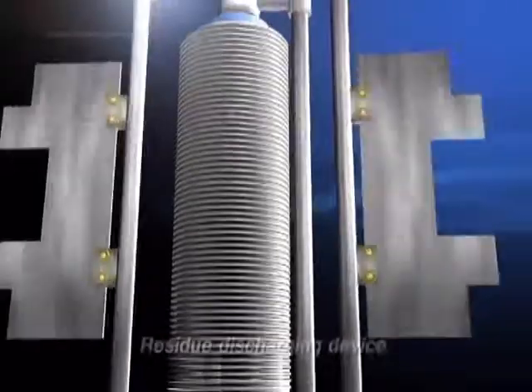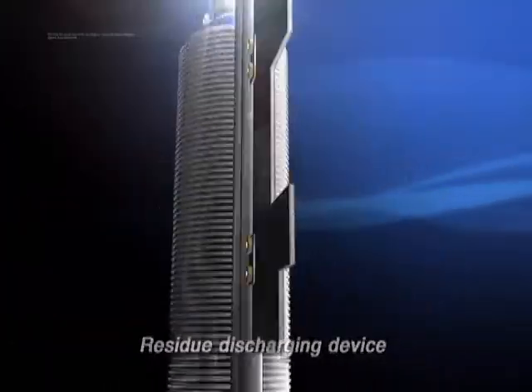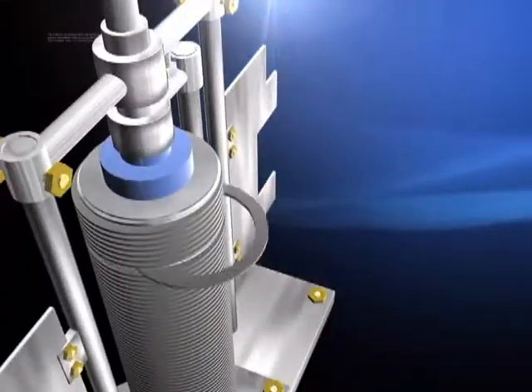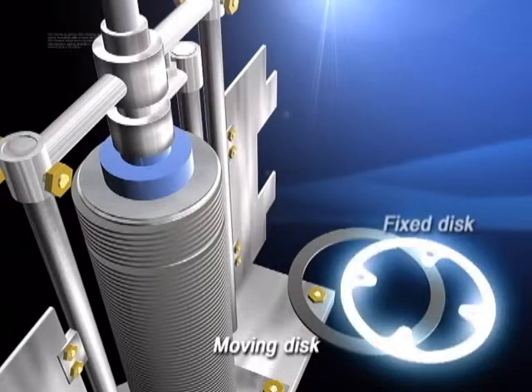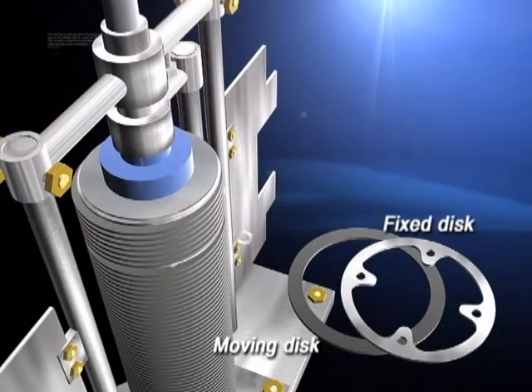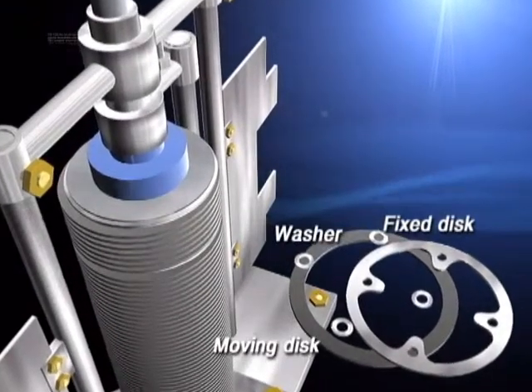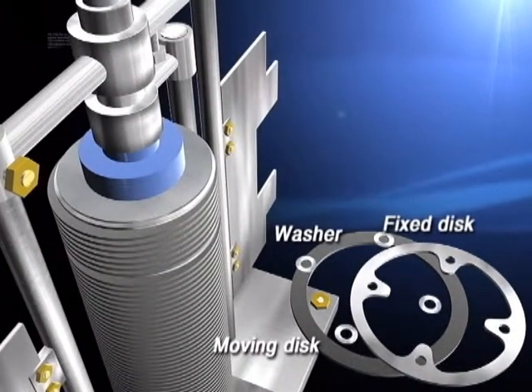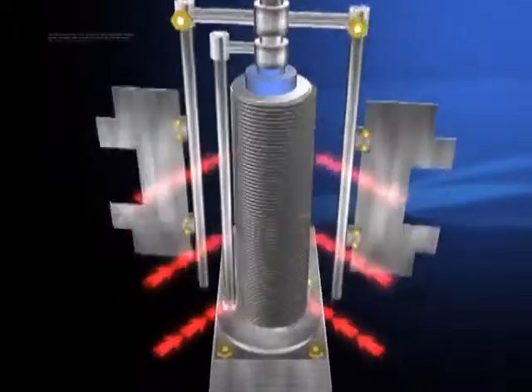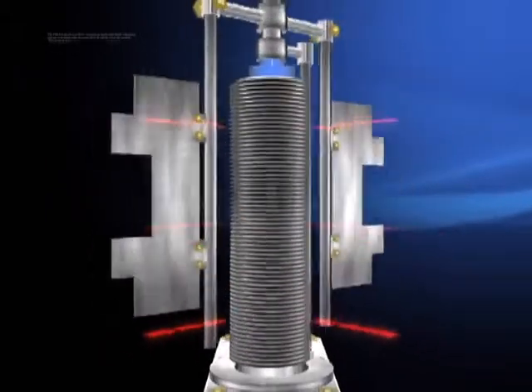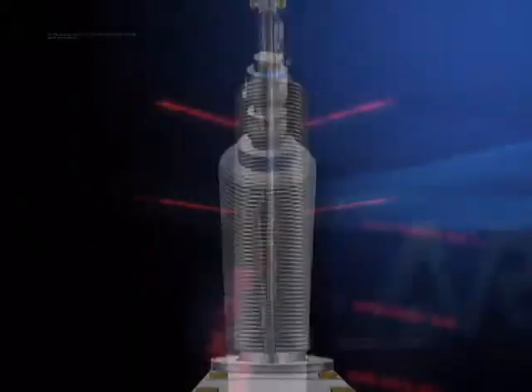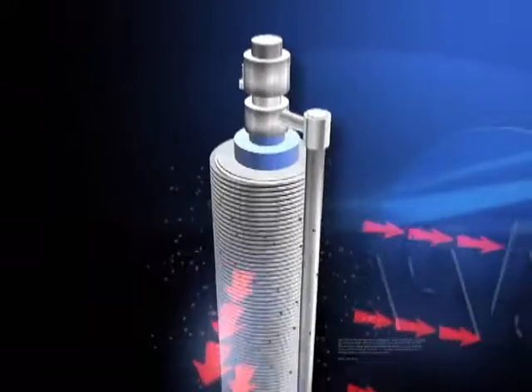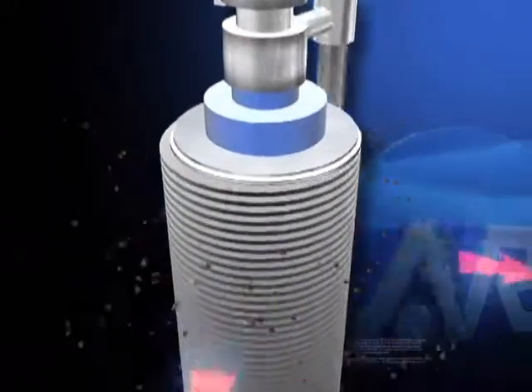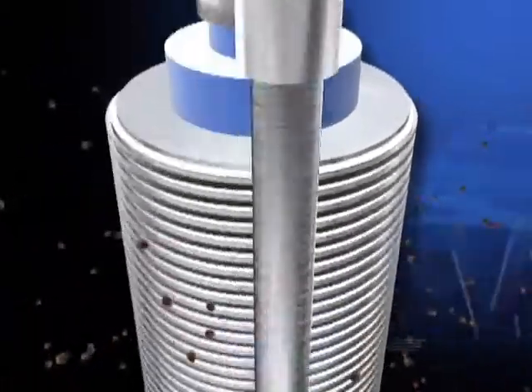The residual discharge device is composed of moving discs and fixed discs driven by a scraper. Washers are placed between the discs to ensure regular gaps. This gap is thus formed to discharge residual liquid in the midst of the concentration process. When the scraper rotates, it removes any floc stuck to the surface of the disc and prevents clogging of the gap during moving of the disc.